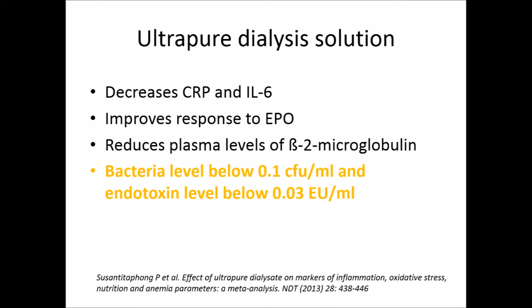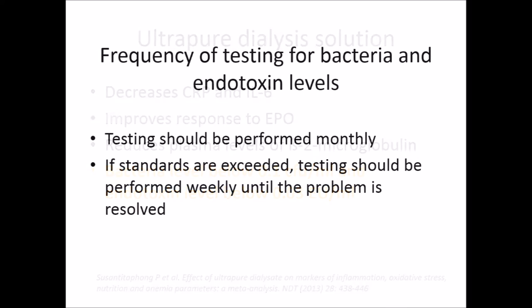Coming to ultrapure dialysis solution — we all know the positives: it decreases CRP and other inflammatory mediators, improves response to erythropoietin, and reduces plasma levels of beta-2 microglobulin, among other things. For preparing ultrapure dialysis, the bacterial level should be below 0.1 colony forming units per ml and the endotoxin level below 0.03 endotoxin units per ml. Chemical testing should be done at least once every six months; bacteria and endotoxins should be tested monthly. If standards are exceeded, testing should be performed weekly until the problem is resolved.